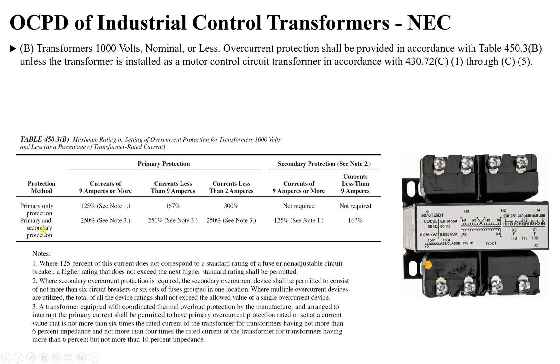However, this transformer type has a specific special case: overcurrent protection shall be provided in accordance with the table unless the transformer is installed as a motor control circuit transformer in accordance with NEC 430.72(C), items 1 through 5. Of these, item C4 is particularly important.